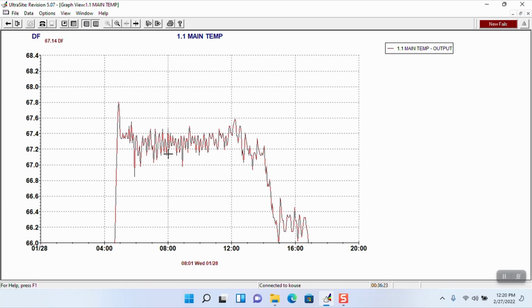I mean, you want to try to smooth that out. You don't want those peaks and valleys. See, they go up and go down. You want it to be almost flat and maybe like a tiny bump above and a tiny bump below. I mean, you're never going to get it perfect. For what we're doing, we don't need that. We're not controlling conveyor belts and robots and stuff like that. We're controlling temperature and pressure. We have a degree or two or a PSI or two of leeway on it. So that is how we do the PID loops inside a loop sequence controller.